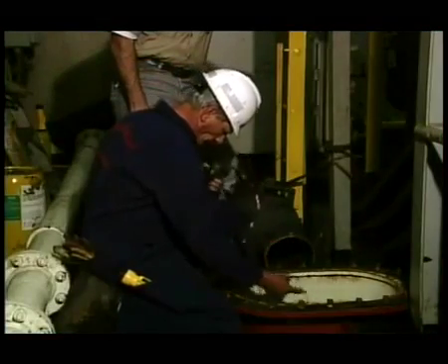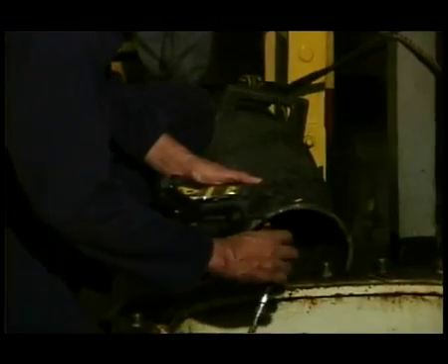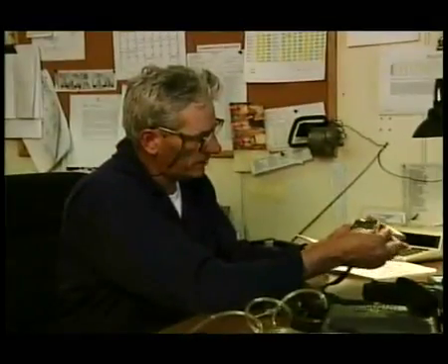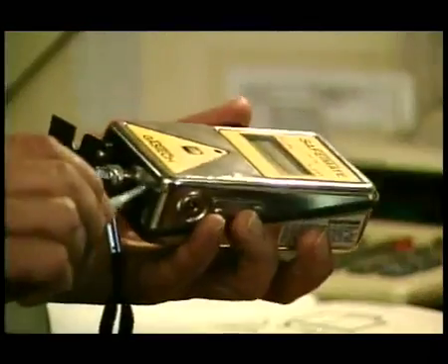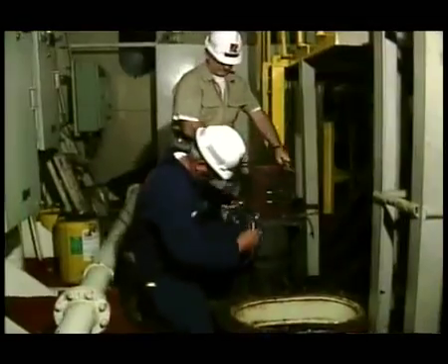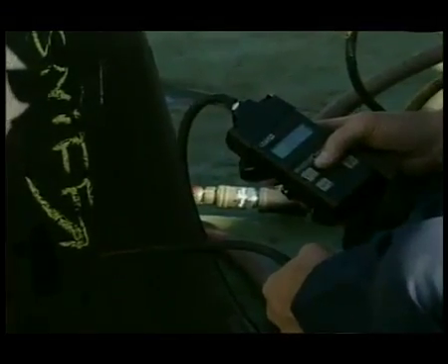Because hazards are not always detectable by odor or sight, it is imperative to test for hazardous conditions prior to entering confined or enclosed spaces. All testing instruments must be properly calibrated and maintained as per the manufacturer's instructions before testing can begin. Initial testing shall be performed by drop tests or the insertion of sample probes or hoses.